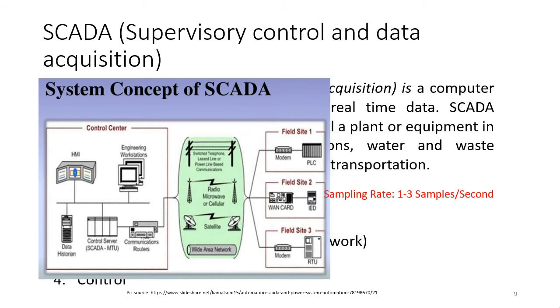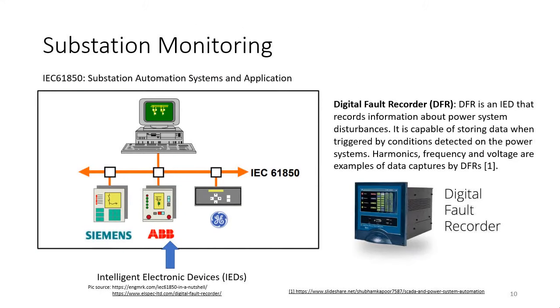Since this monitoring system was designed for a substation in a petrochemical facility, one protocol you have to use is IEC 61850. This is a substation automation protocol for substation monitoring. The reason they developed this protocol is because you have different IEDs.